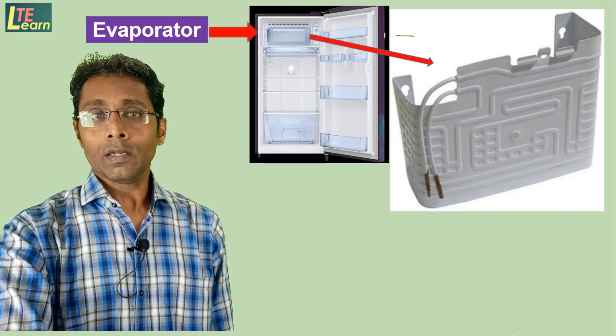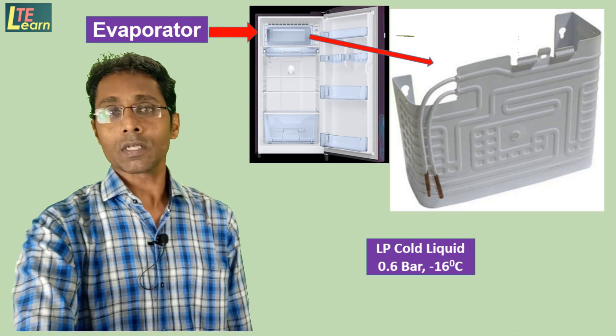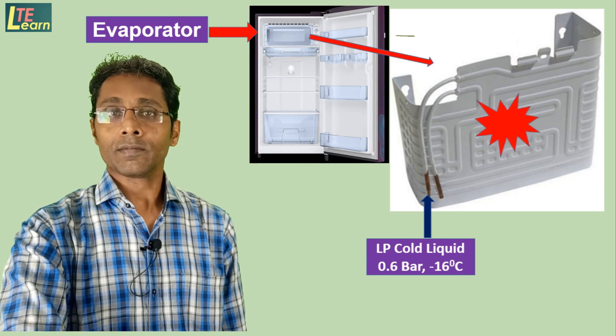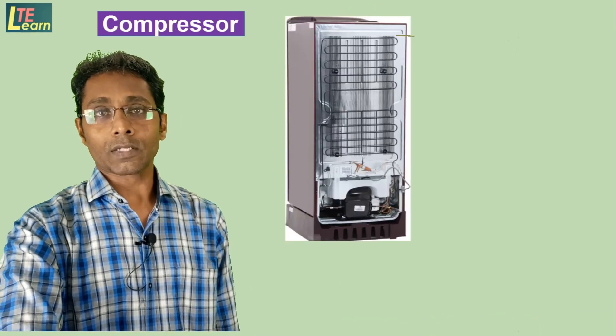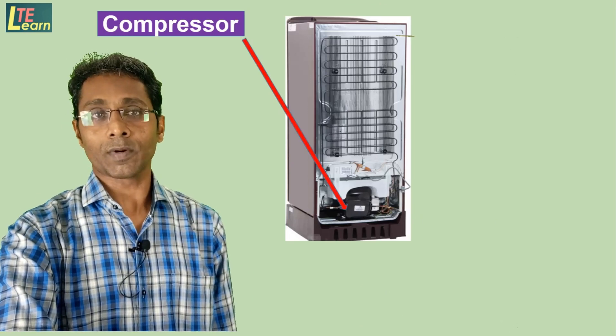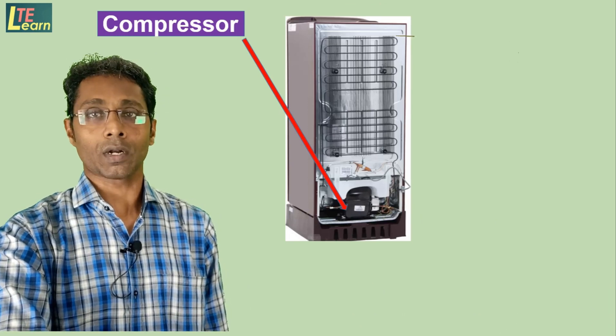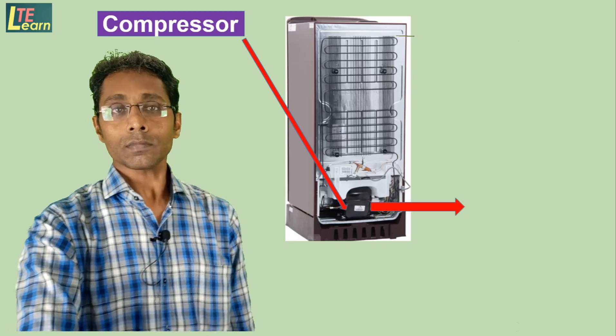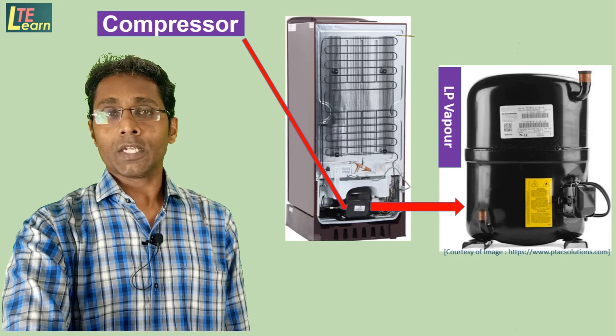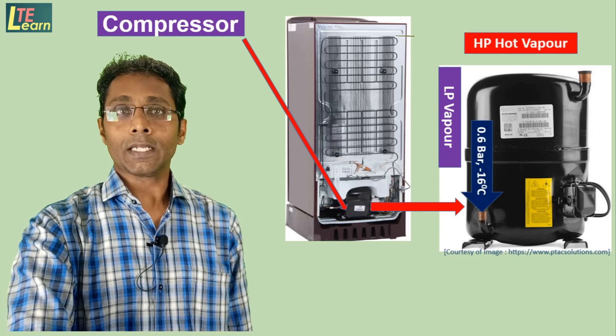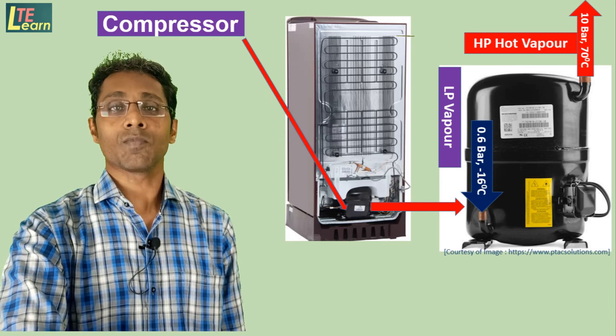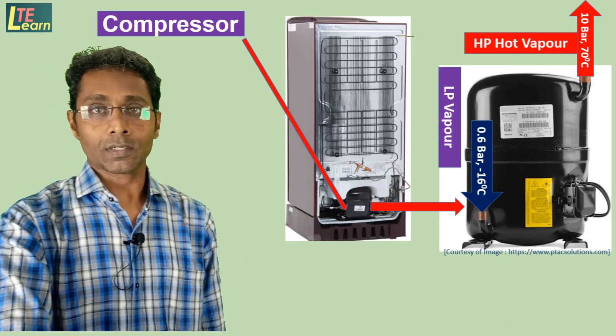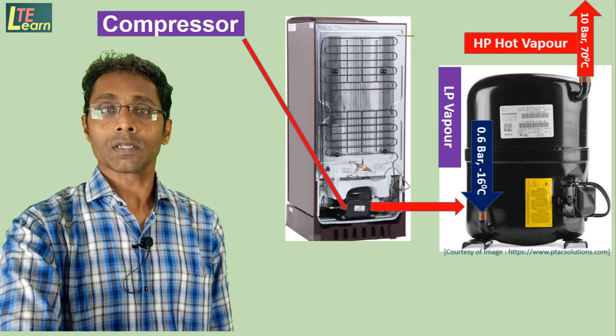The evaporator is situated at the freezer section. When this low-pressure liquid refrigerant passes through the evaporator coil, it absorbs heat and changes phase — it becomes vapor. This vapor then goes to the compressor, which is situated at the back side of the refrigerator at the bottom level. The function of the compressor is to increase the pressure of the refrigerant. The low-pressure vapor is converted into high-pressure vapor, its temperature also increases above the atmosphere, meaning its thermal energy level is increased, making it possible to reject heat from this vapor refrigerant.